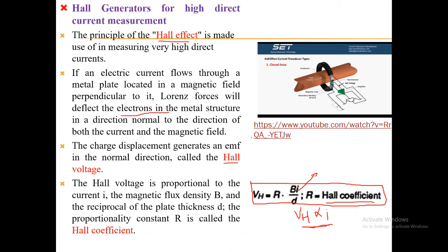After repeatedly adjusting the output current of the amplifier, the magnetic field generated by the primary current and the magnetic field generated by the secondary coil will be the same strength but opposite direction at the air gap, so that the Hall element is in a zero-flux environment. When reaching this equilibrium state, the amplifier output current can represent the primary current.